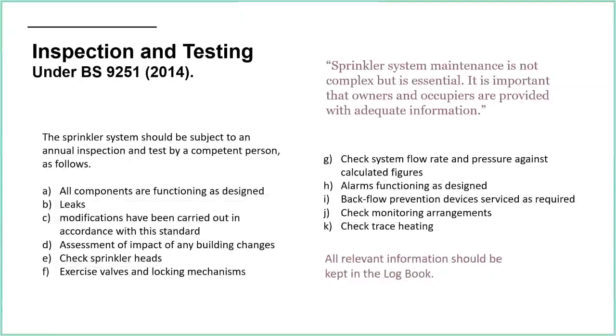Checking the sprinkler heads. We've been through that in a previous presentation. Checking for damage, checking for paint, checking for corrosion, any other issues with the sprinkler heads, checking that they're not blocked or obscured. Exercise the valves and locking mechanisms. Check system flow rate and pressure against calculated figures. So that's the test I was talking about, this full flow test. Generally speaking, that is at the fire pump. If your fire pump is delivering the specified flow rate at the specified pressure, then everything else should be good because it's all based on that design.